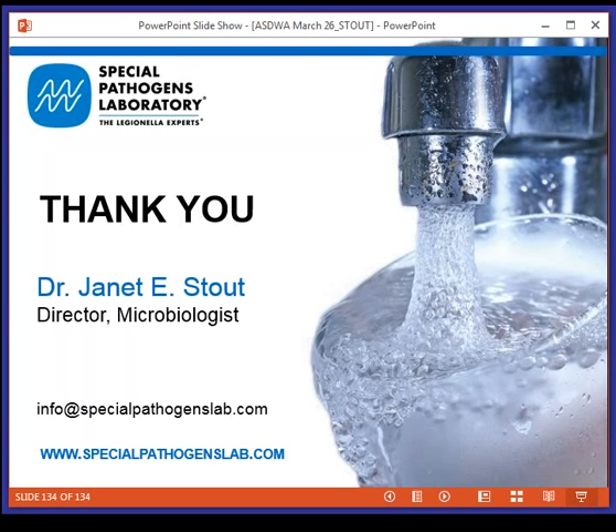Well, what we found was that the UV unit scaled up. The quartz sleeve that the lamps are in would scale up because our drinking water has scale-forming capability. So then we put a pre-filter on it, so there's a pre-filter before the UV unit, and then disinfected downstream. And we found that the outlets would stay negative for Legionella for about 3 months. And then Legionella would come back, basically because of the rebound after chlorination. So the UV unit certainly can improve water quality, microbiologically speaking, as that water goes through it.